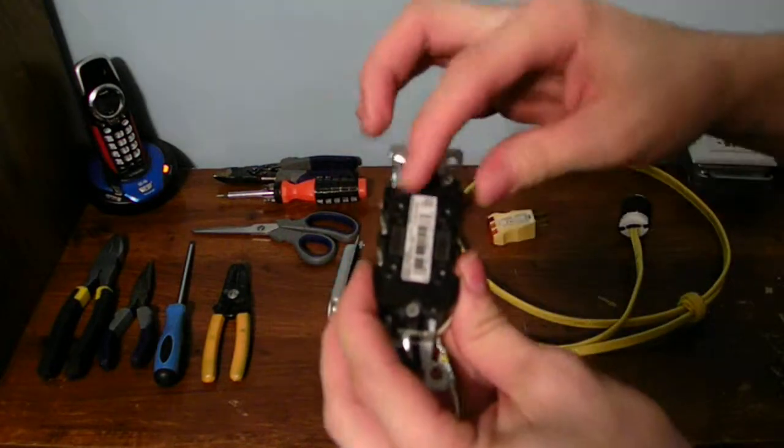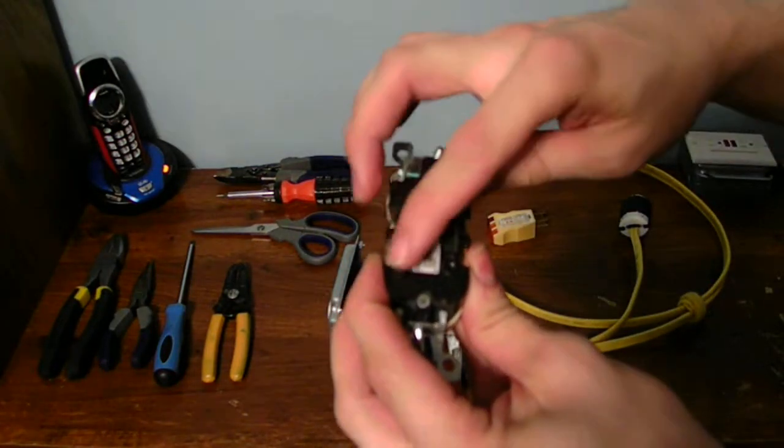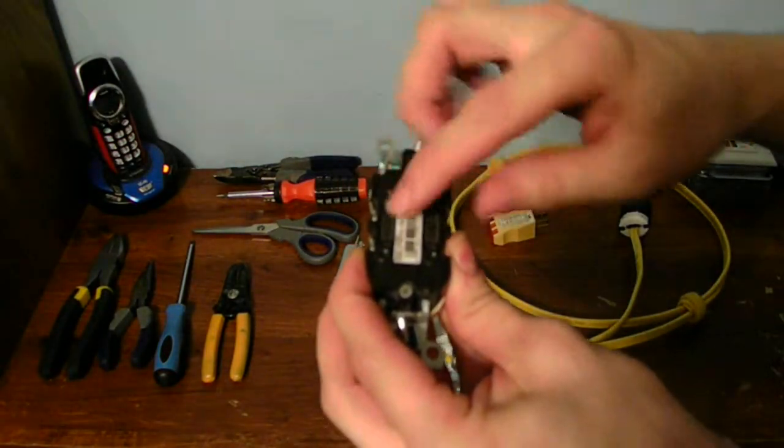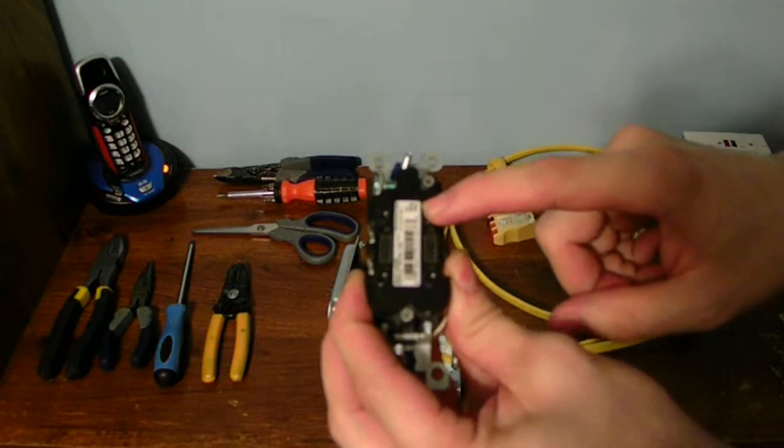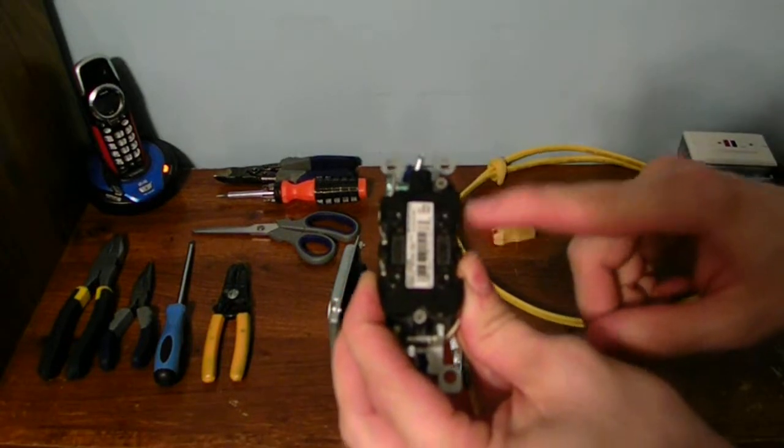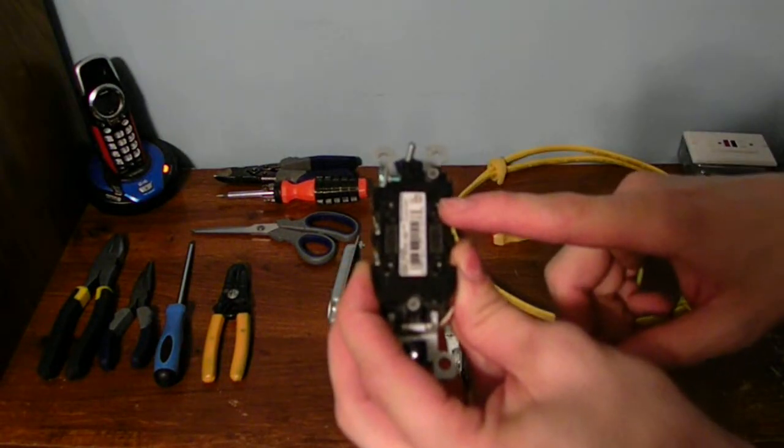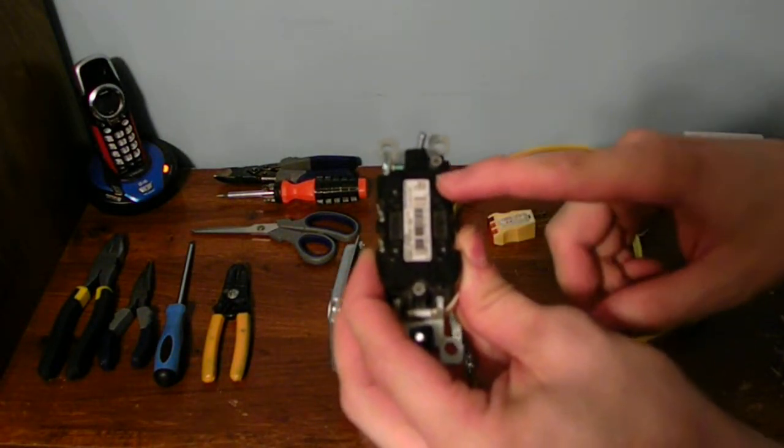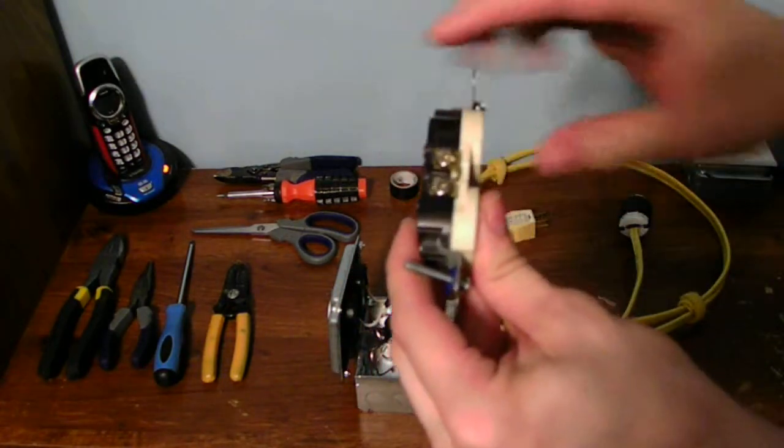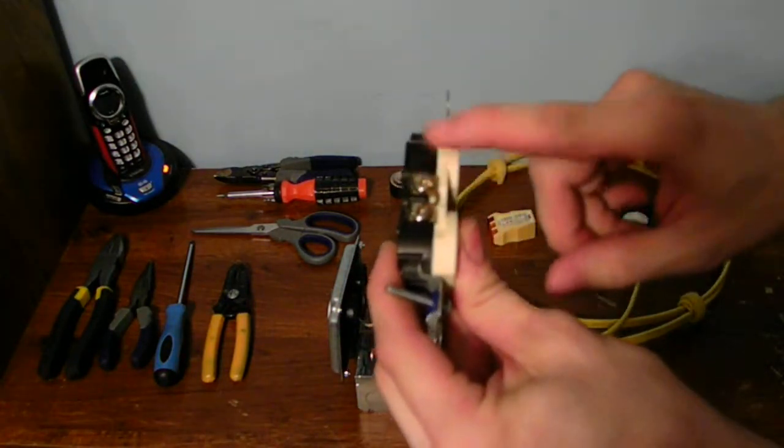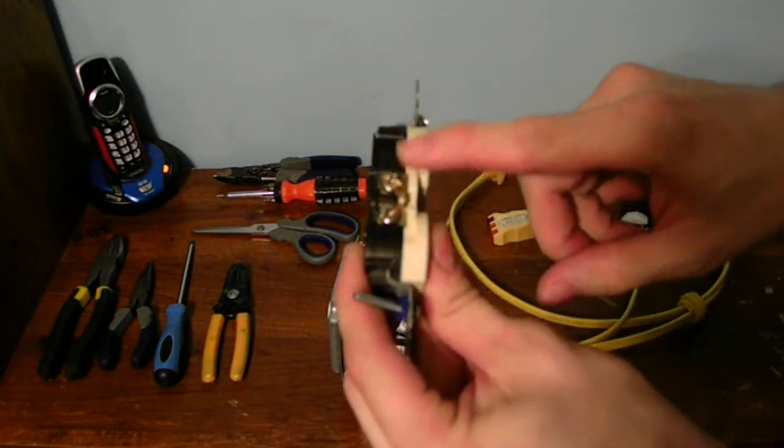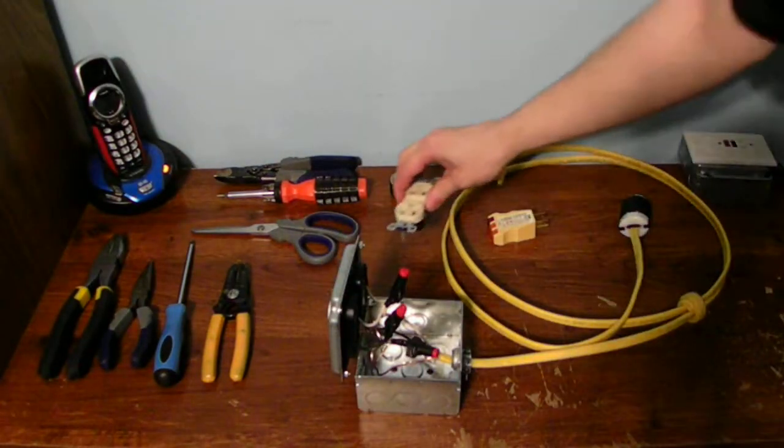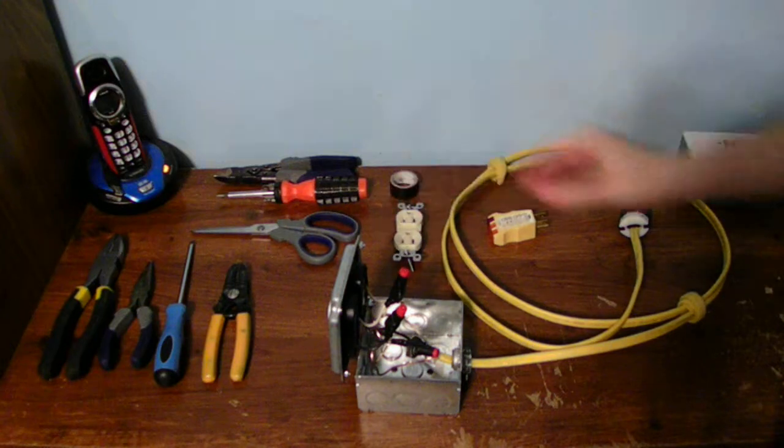Now on the back of these, these have these lazy push-in connectors. I don't recommend using those at all. Those are only meant for a 14 gauge wire, but not 12. These are a much better solid connector right there as well.